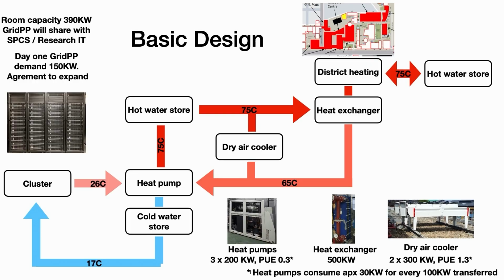If it can't go into the district heating system, we have 2 300 kilowatt dry air coolers outside, which we can put it to the atmosphere. And that can work all year round because the water going into those dry air coolers is 75 degrees. To put that into some kind of picture, this is what is happening. The cluster produces hot water into the heat pumps, goes into the hot water store, so we can store it in the room, into a heat exchanger, into the district heating system. They have additionally been building additional water tanks around campus, so they've got several 3,000 litre tanks to store the water. There's about 10 buildings presently connected to the district heating system, including residences and catering departments.